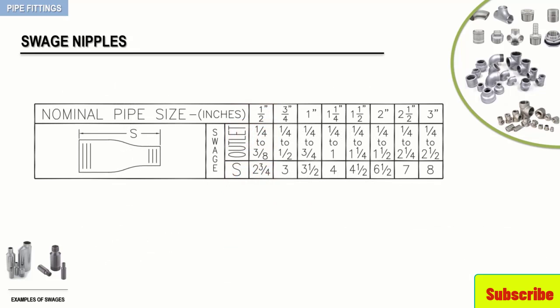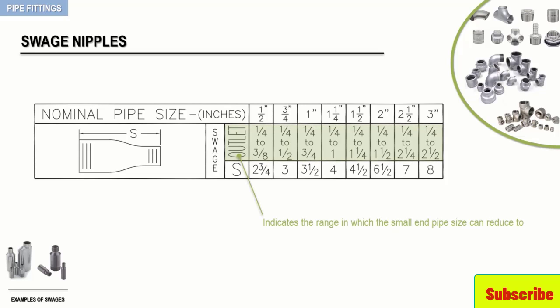The following dimensioning chart provides the length or S-dimension of swage fittings as a function of the pipe nominal size. Like reducers, you must always use the large end pipe size to find the length of the swage on the dimensioning chart. The outlet section of the chart simply indicates the range in which the small end pipe size can reduce to — it does not affect the length of the fitting.